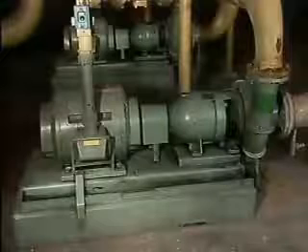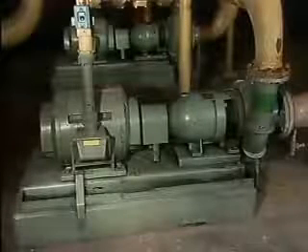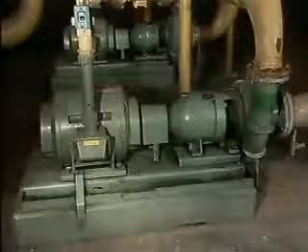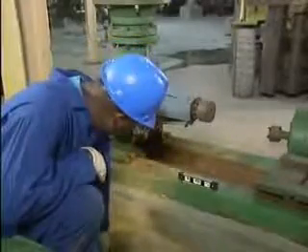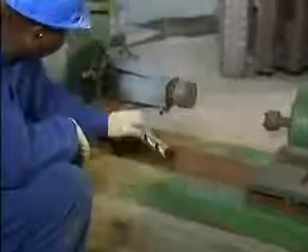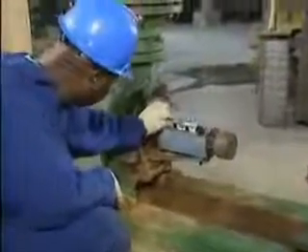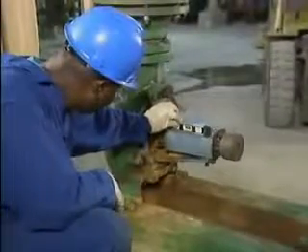One basic check is to make sure that the foundation is large enough to adequately support the equipment mounted on it. The foundation should also be checked to make sure that it's level. One way to do this is by using a bubble level. If the foundation isn't level, you should verify that the stationary component has been properly shimmed to make it level. This can be done by placing the bubble level on the shaft or other horizontal surface of the stationary component.